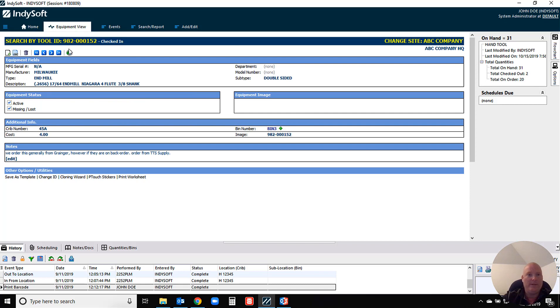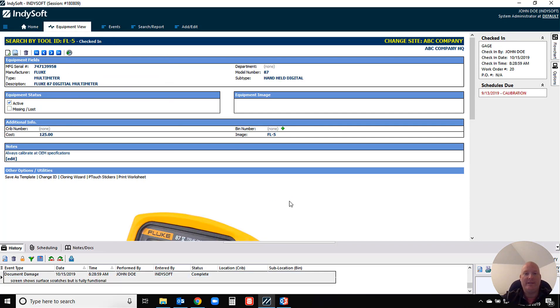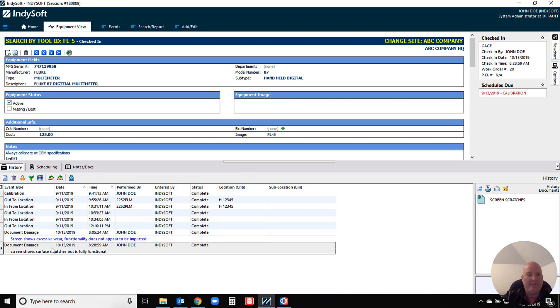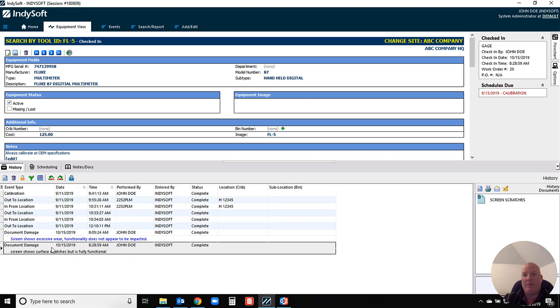And then in the example that we did earlier with the Fluke 87, I definitely think that just having the ability to document damage to items when it's there, you can either do that in a separate event like I did in this illustration, or for our commercial labs it may be good just to have an option to do that in your receiving events, potentially in the calibration event as well if the technician is the one who notices the damage.